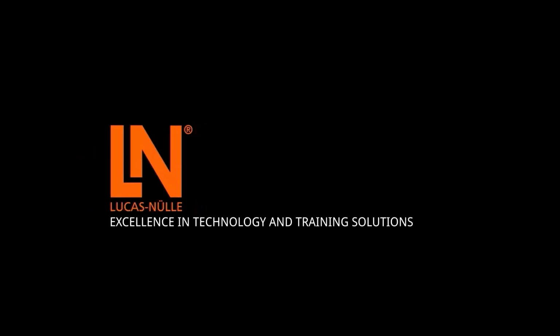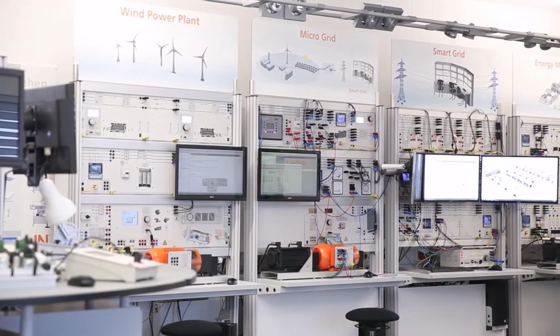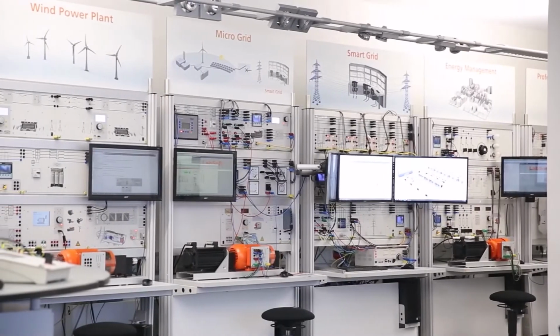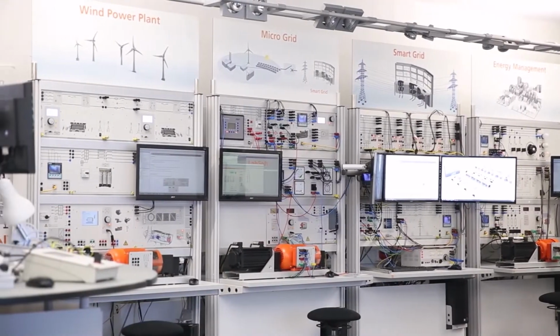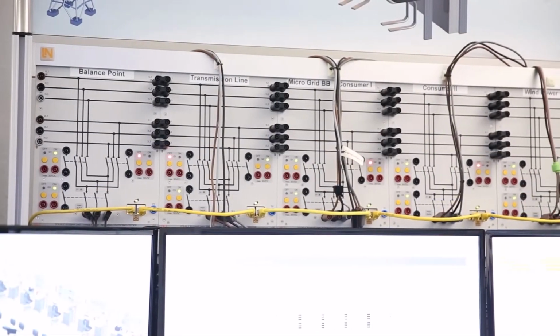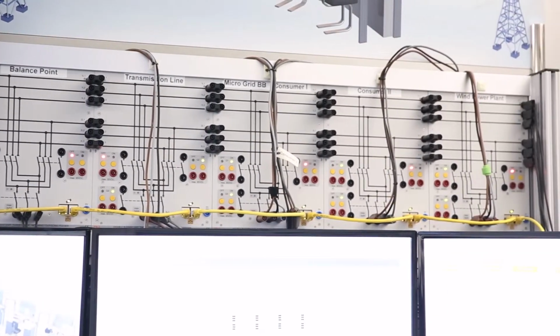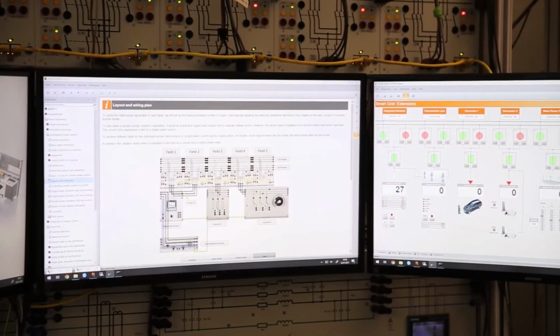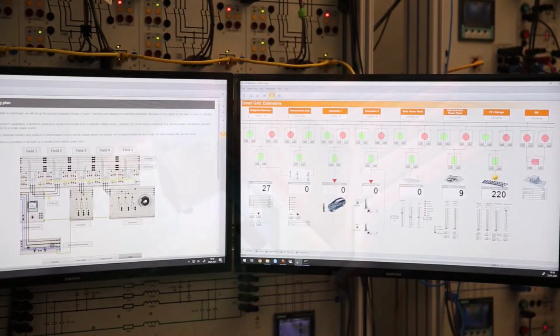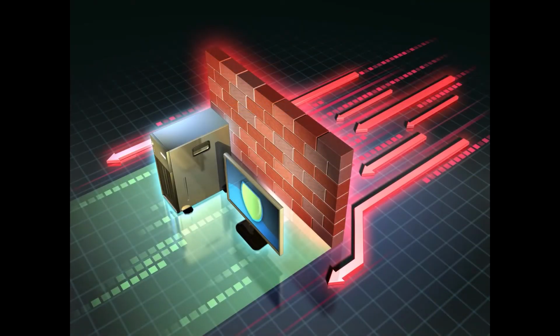In this video, you will learn how to reconfigure or modify the firewall rules to ensure the functionality of the software. Typically, all the computers or equipment inside a laboratory are interconnected via network switches without any further local network connection. Since no standard gateway is involved in this type of infrastructure, Windows identifies the local lab network as public. The local server ports will be blocked even if the Windows firewall is disabled.